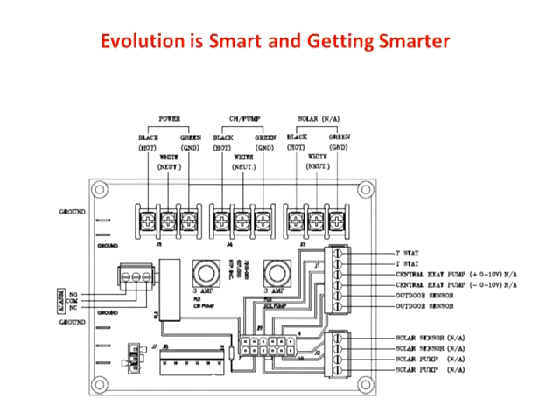But if you start over here on the left, we just have power coming in. We have the standard pump on the system. And where it says NA, that's for the future, where the solar pump will be, meaning that with the Phoenix Evolution Solar, next year you'll have a module for the solar built into it, and it'll all be fully controlled by this one control. Lower side here is the T-stat, either directly a thermostat or more likely off a switching control, so whatever your switching control strategy is, pumps or not.